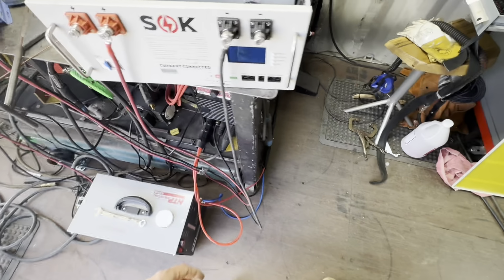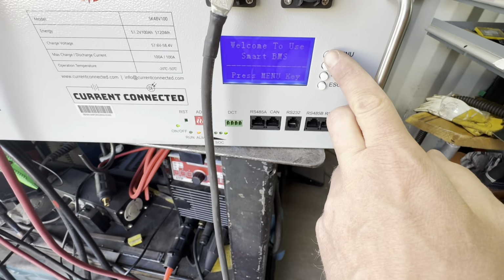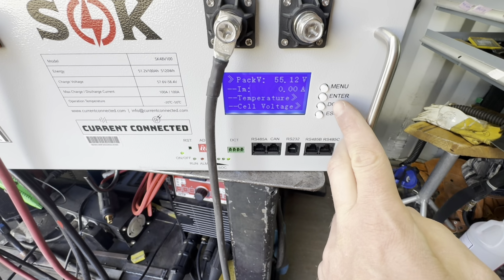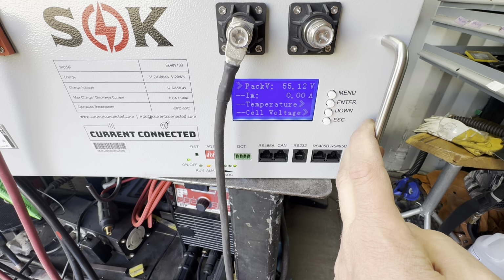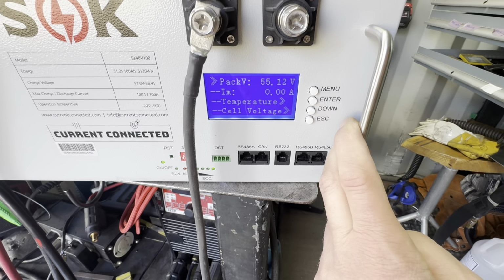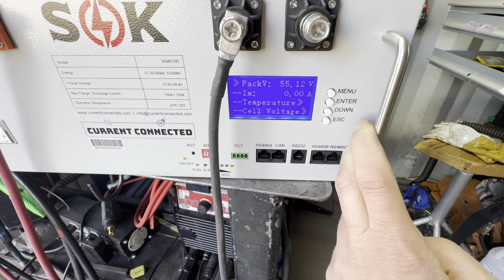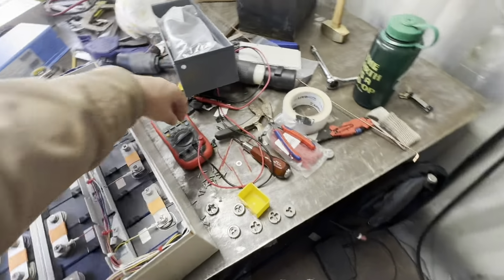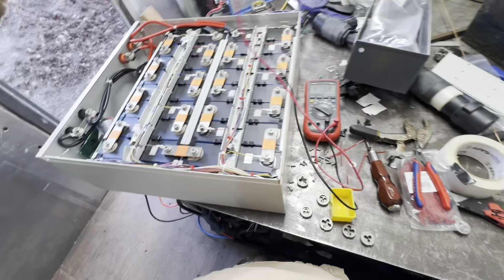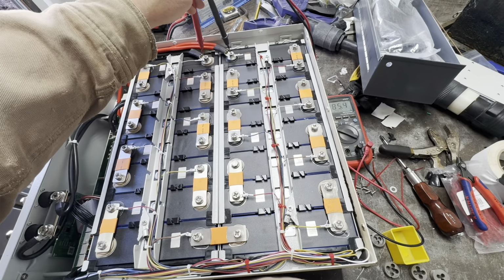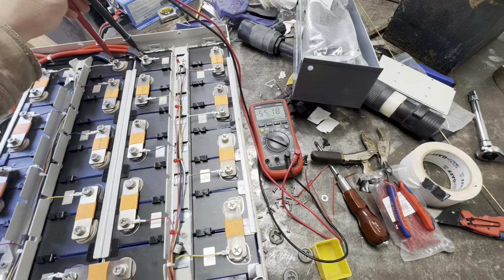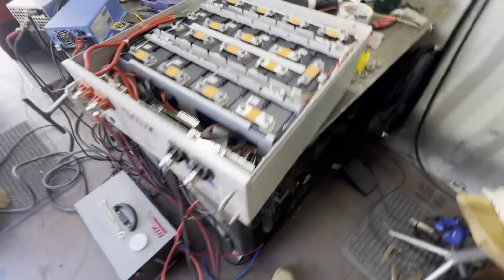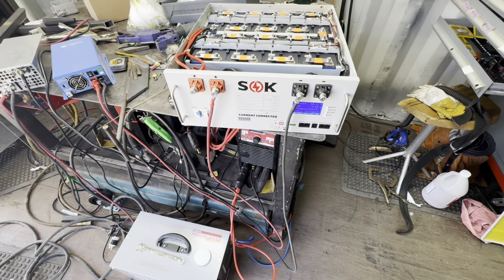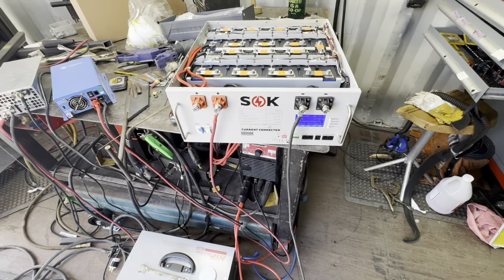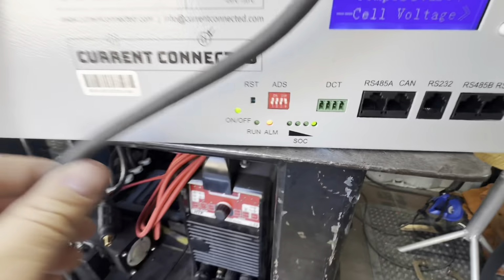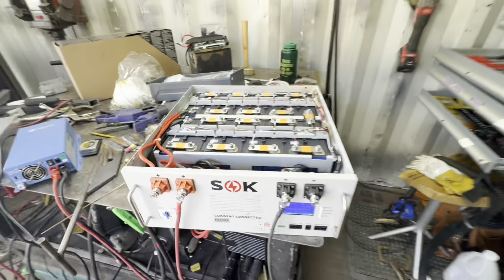But now I'm trying to get it going here, and it looks like it stopped charging, which is cool. It's showing 55, and I'm showing backwards polarity, 55.2 I think. 55.11, it's really close, but it's still giving me the alarm, and it's also still showing state of charge as low, so maybe it needs a reset.